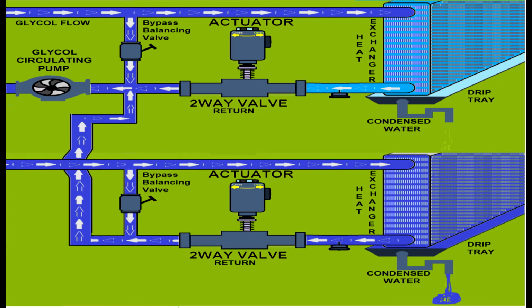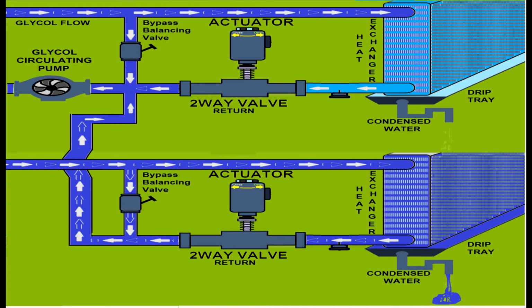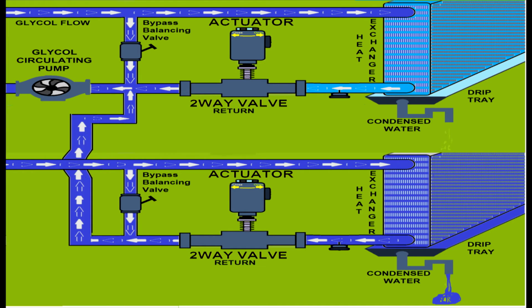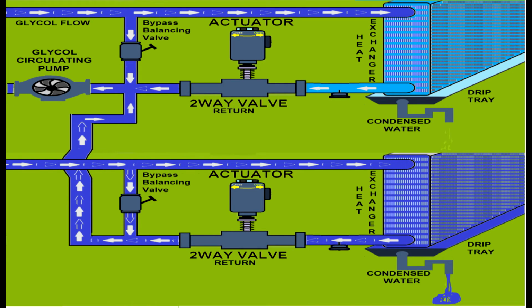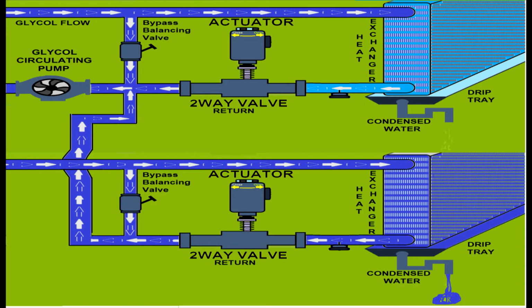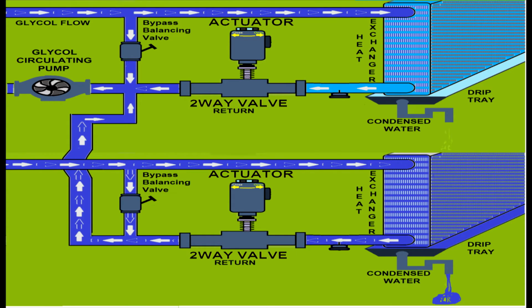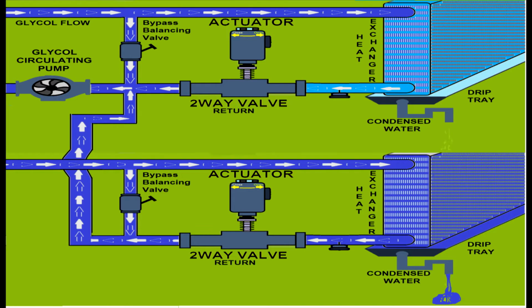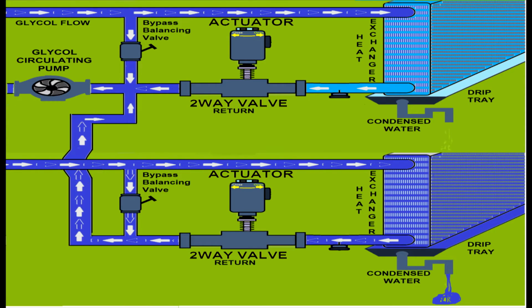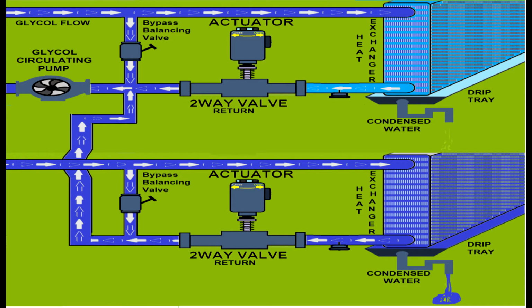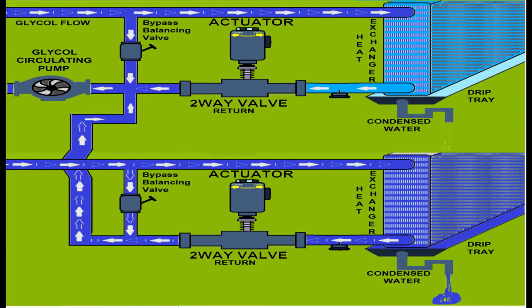If you look at the drip tray, it's empty for the top one. The bottom one, it's got water, so the bottom heat exchanger runs below the dew point. This system, it's okay, you have one pump, you have the glycol circulating through both heat exchangers, and you have actuators which control the capacity of each heat exchanger, allowing more or less glycol to pass by.